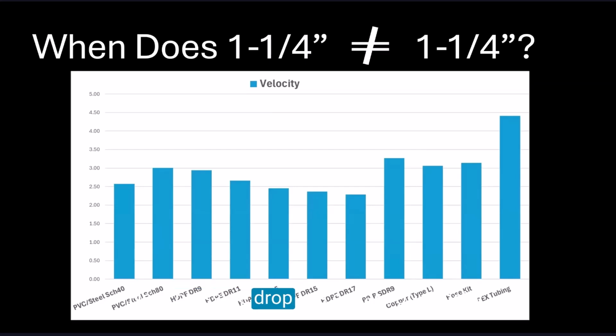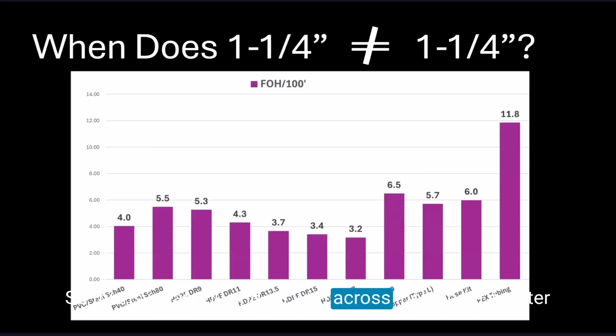Now, pressure drop is a square of velocity. So this is what you end up with across 1.25-inch pipes or tubing. And there's tremendous difference. And I don't believe many people really calculate pressure drops looking closely at these numbers. So that is what drove us to try to develop a piece of software that can help tackle these calculations as accurately as we're tackling loads and loop length.